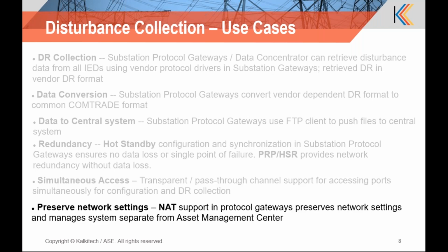Then another key use case: many utilities have their own network settings for a substation, which are not unique when viewed from the center. So one substation having an IP address may get repeated on another substation. So connecting from the center and configuring the IEDs using the same IP will not be possible from the central side.